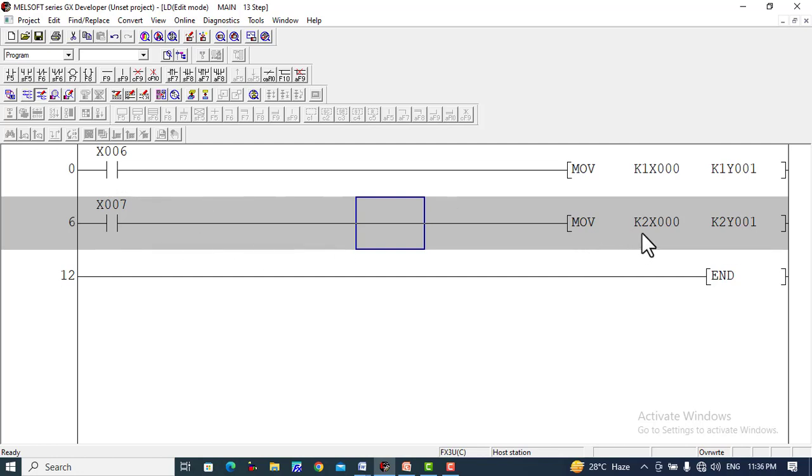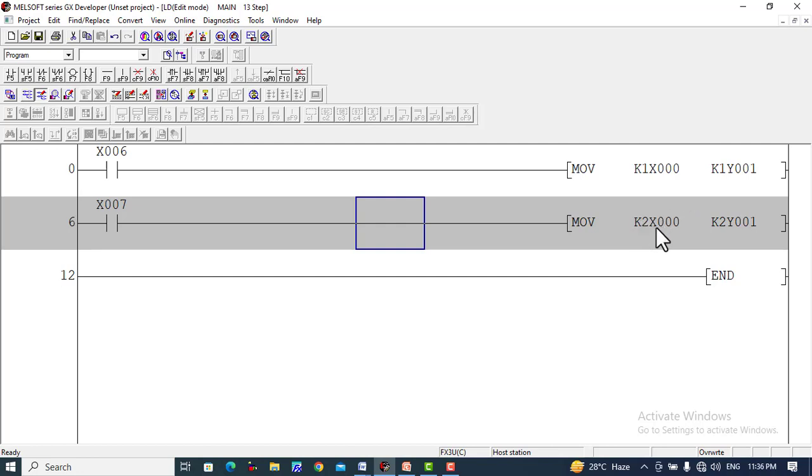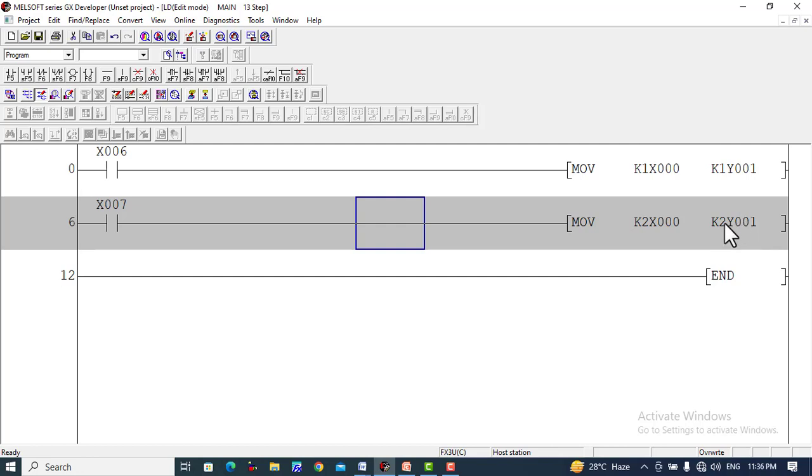In a similar way, when you use K2, it represents eight values. For example, when X7 is turned on, K2 represents eight values starting from X0, X1, X2 up to X7. When K2 is written in this form, it will take the values from X0 to X7 and correspondingly turn on the values Y1, Y2, Y3, Y4, Y5, Y6, Y7, and Y10. It goes in octal form, so after Y7 it will turn on Y10.